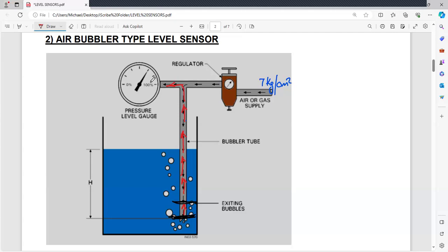And that will be going to a local indicator, which will have a pressure transmitter, because pressure is going to be acting on this, isn't it? So it will be a pressure transmitter. As the level is increasing, so also would the back pressure be acting on the diaphragm of this particular indicator, and accordingly the pressure transmitter is then going to transmit that signal to a remote position, in this case your cargo control room, as to what is the level within this tank.